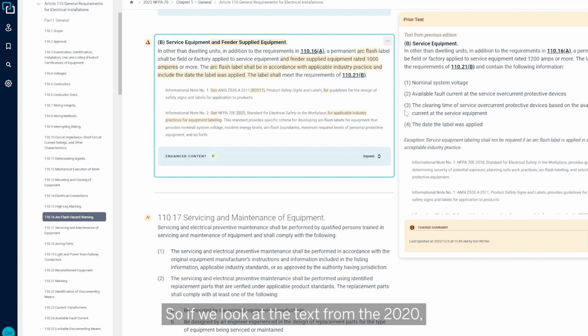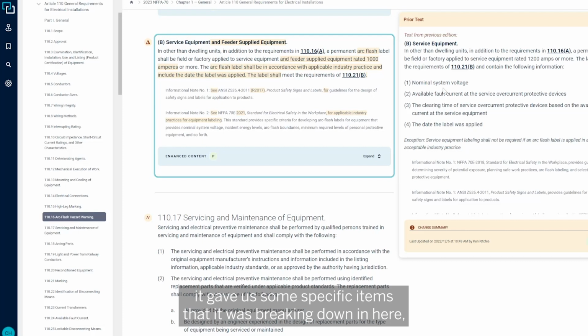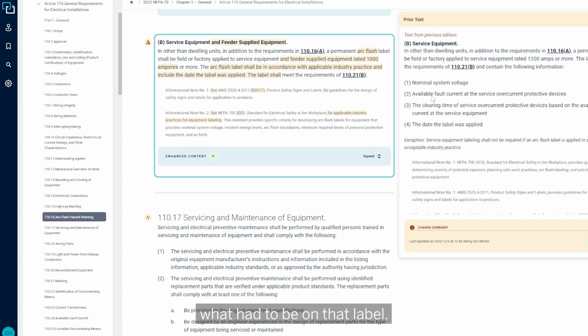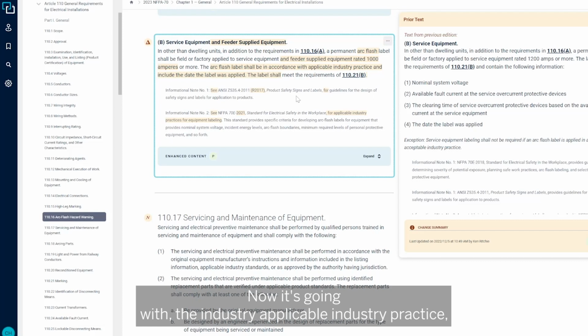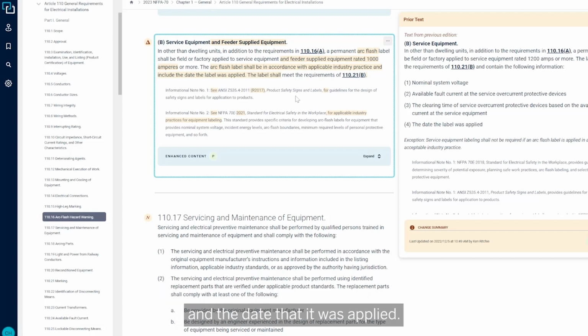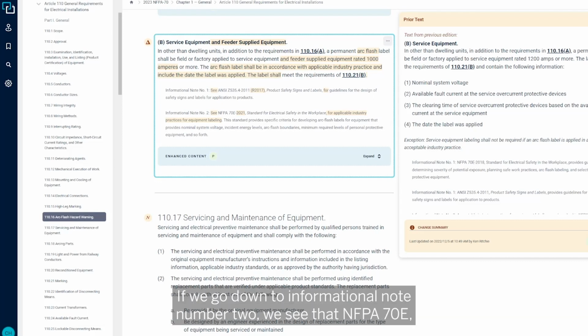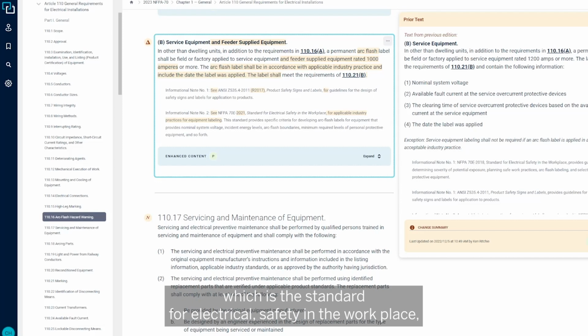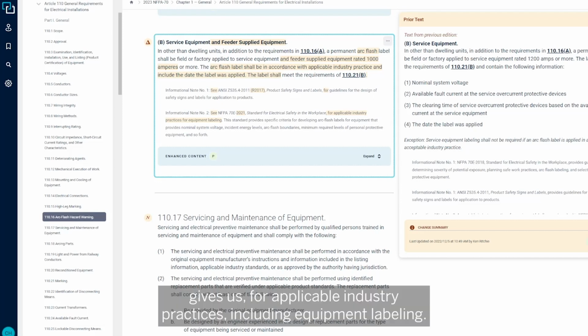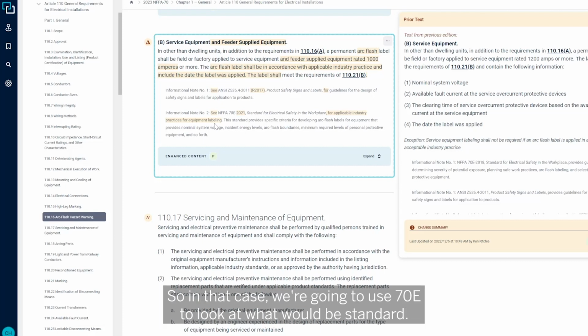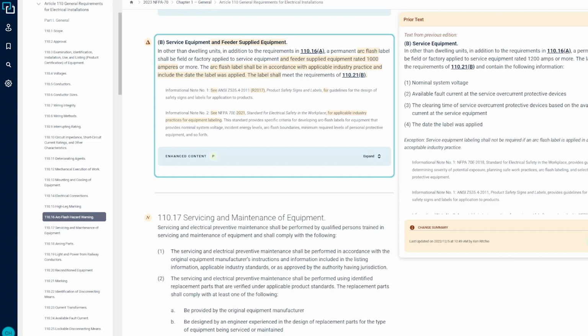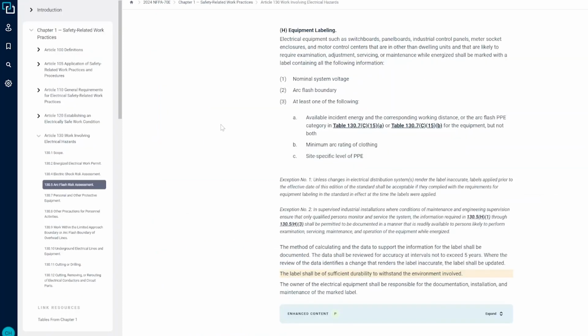So if we look at the text from the 2020, it gave us some specific items that it was breaking down in here, what had to be on that label. Now it's going with the applicable industry practice and the date that it was applied. If we go down to informational note number 2, we see that NFPA 70E, which is the standard for electrical safety in the workplace, gives us applicable industry practices, including equipment labeling. So in that case, we're going to use 70E to look at what would be standard. And I already have that open over here.